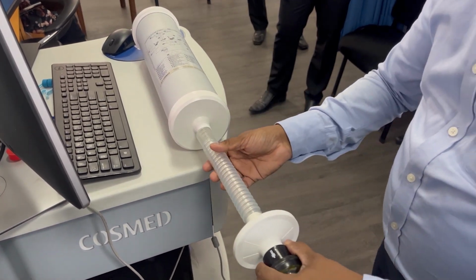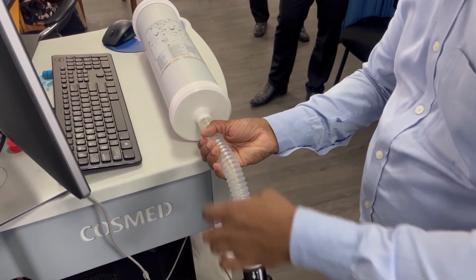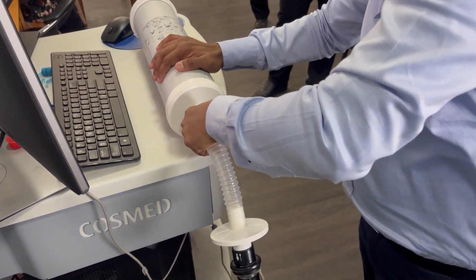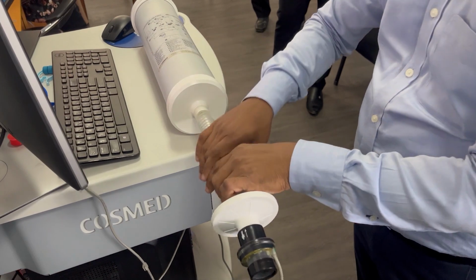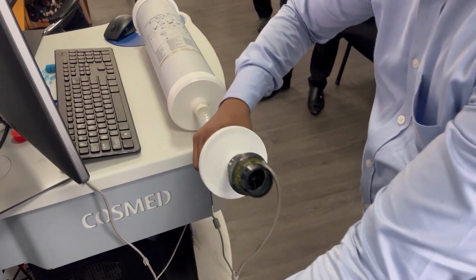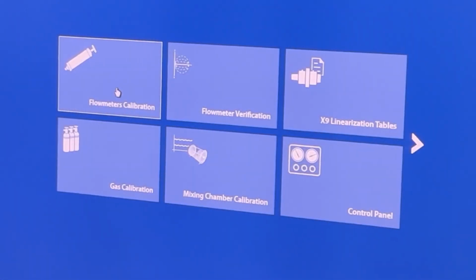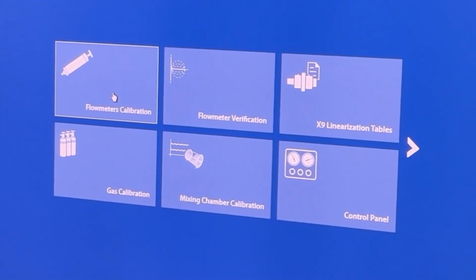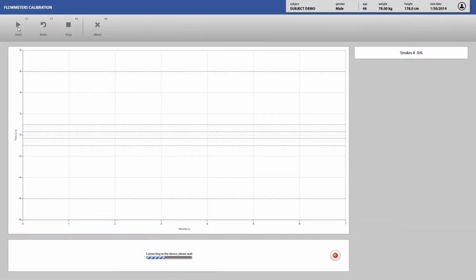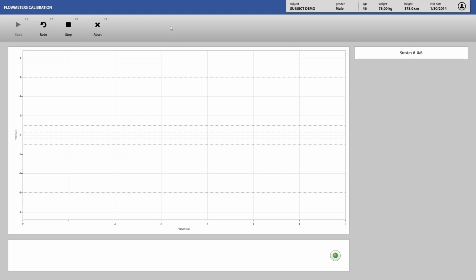During volume calibration, it is good practice to use viral filters and other hygienic precautions to prevent cross-contamination by the syringe. A range of flow rates should be performed to simulate the wide range of flow rates that occur in going from rest to heavy exercise.